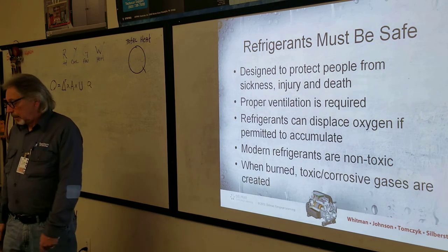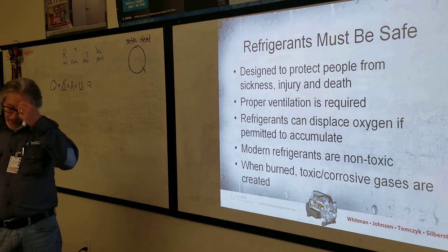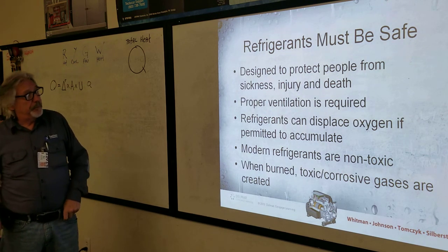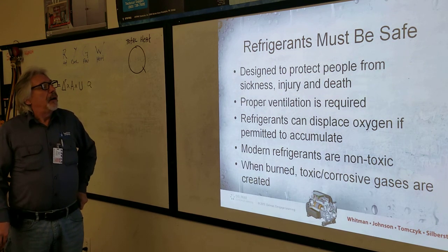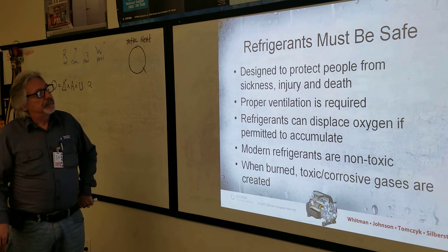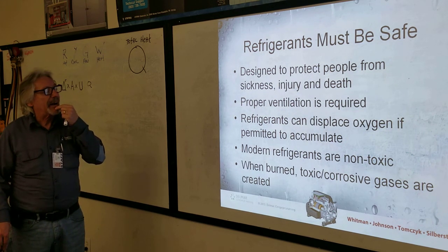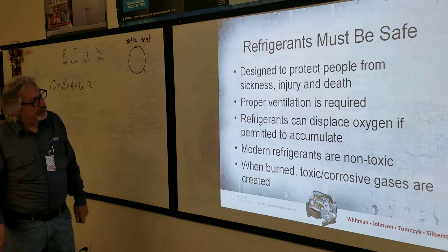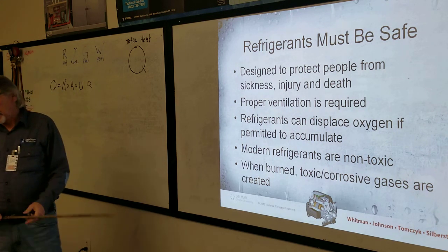Refrigerants must be safe. Designed to protect people from sickness, injury, and death. Proper ventilation is required. Refrigerants can displace oxygen if permitted to accumulate. Modern refrigerants are non-toxic. When burned, toxic corrosive gases are created.